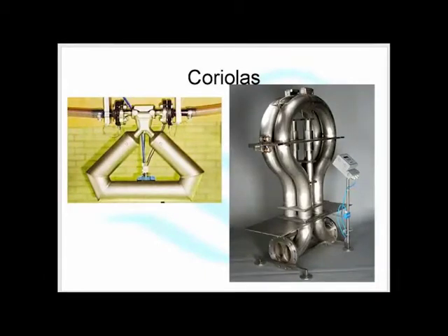Metal fatigue. Yes, absolutely. A Coriolis meter has got a limited lifespan. Not exactly sure how long that limited lifespan is. It's going to depend on what you're putting through it. If you're putting mineral sands through it, you might only get a year out of it.